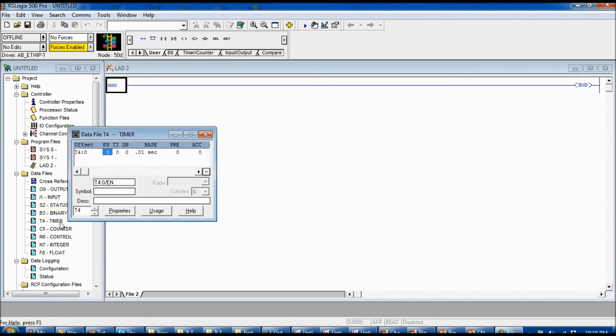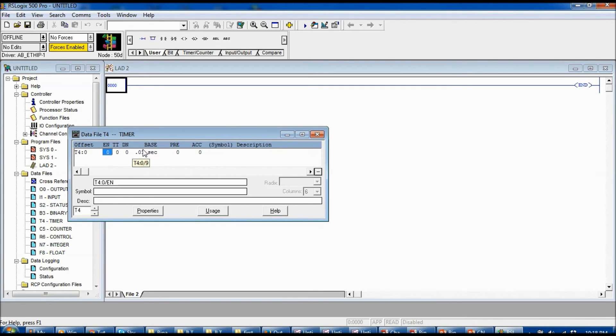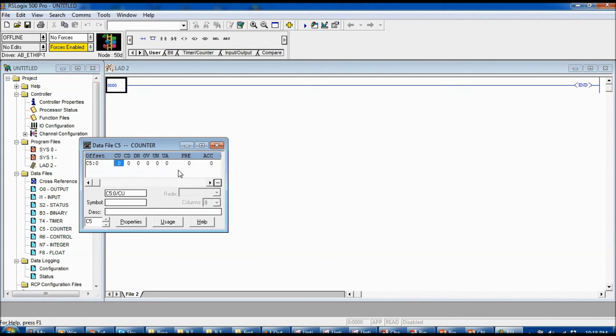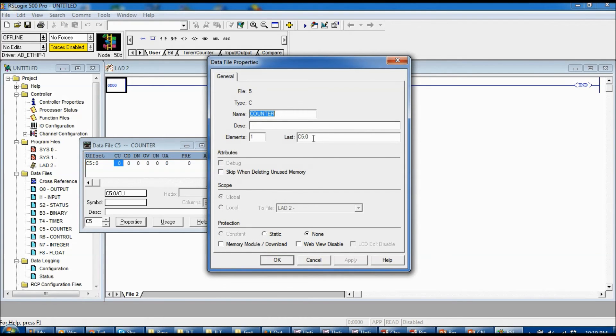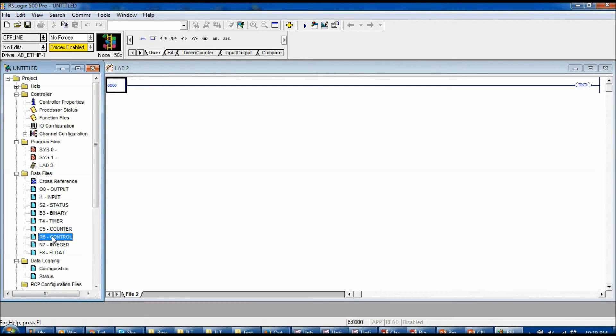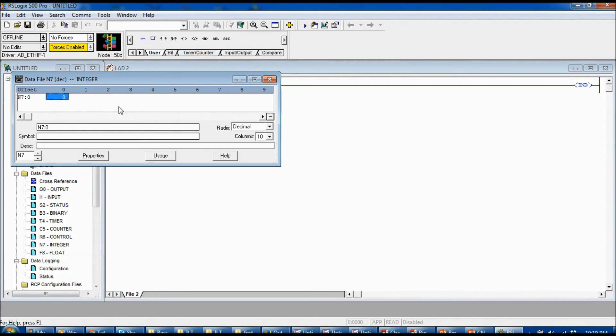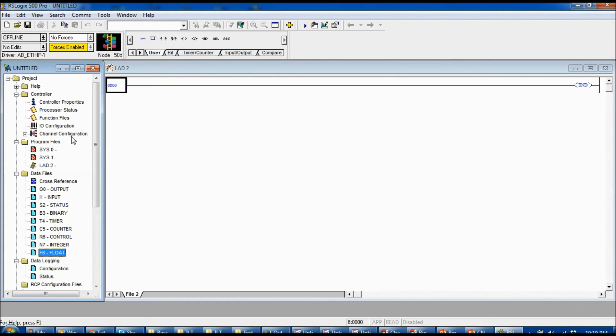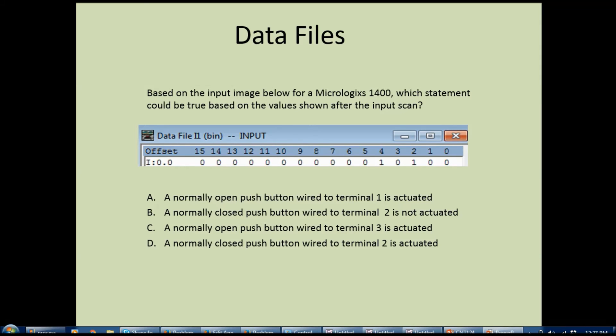Binary bits are just internal memory storage locations we can use to store information - nothing is physically wired like an input or output, but we can use these 16-bit word locations to store information. Here we have a timer - T4 colon zero - and with that timer it has information on each of its bits and words. We also have our counter file; within the counter you have C5 colon zero, C5 colon one, two, three, four, five, and so on - as many counters as the PLC allows. We also have our control file and integer files, which are another storage location useful for passing whole word values.